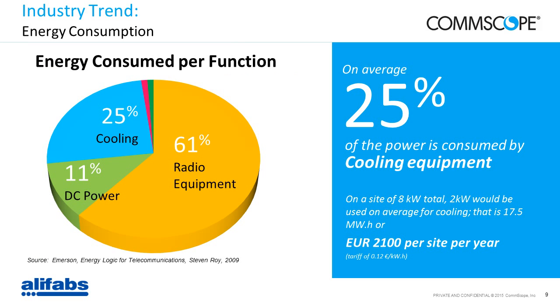So what does that mean for the telecom operators? Well, in terms of energy consumed per function, it's slightly generous from the cooling perspective because we've seen many sites up to 35% of the proportion. But typically on average, 25% of your network will be for cooling equipment, whether it's with free cooling or extractions or with computer room air conditioning, bigger chillers for your data centers, for example. Typically around about 25% of your network will be for cooling.